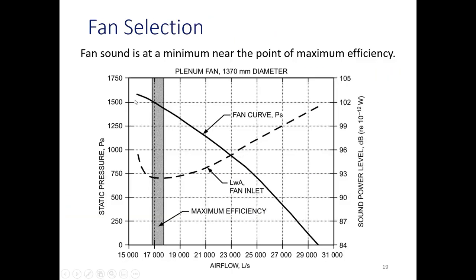So this slide shows this curve here is the A-weighted sound power noise for the fan inlet. And this region here is the maximum efficiency. So the main point is that when it's operating at its maximum efficiency, the noise is going to be at a minimum. So if at all possible, you want to do that.